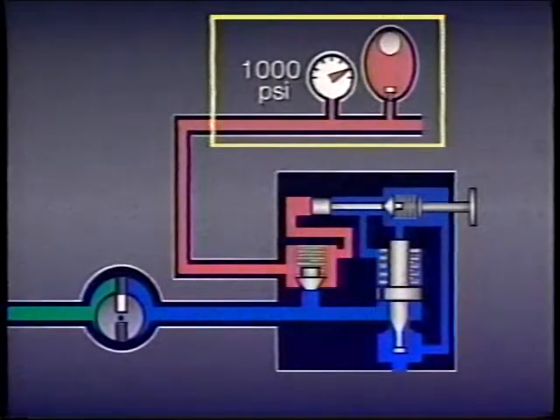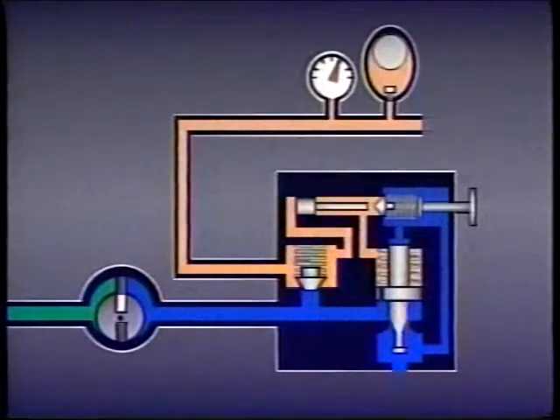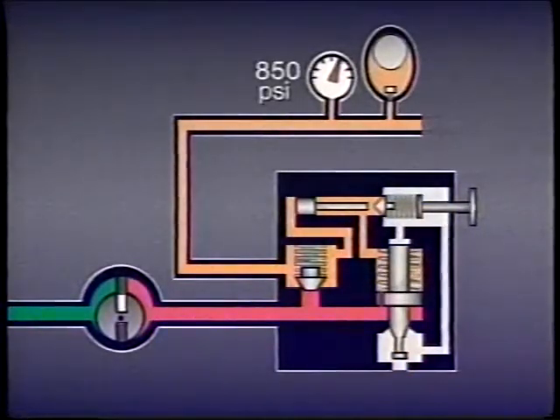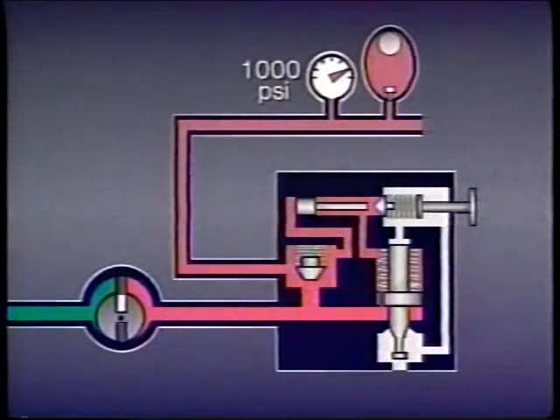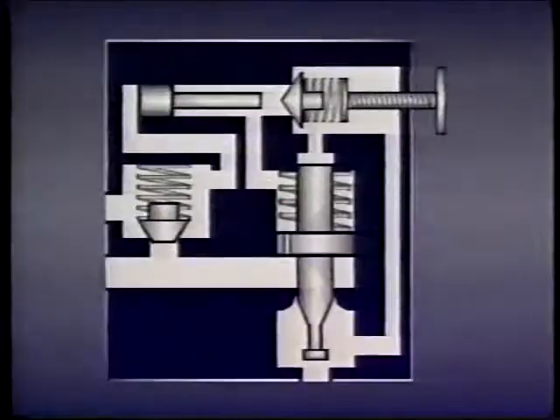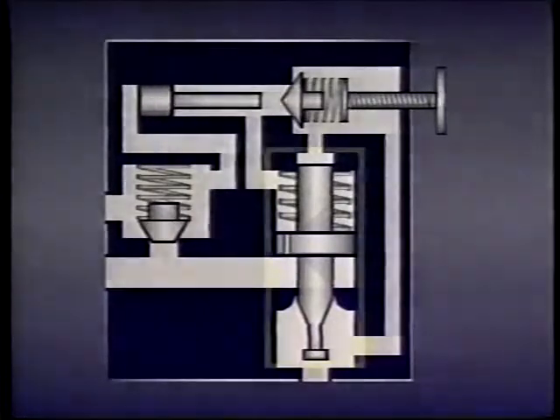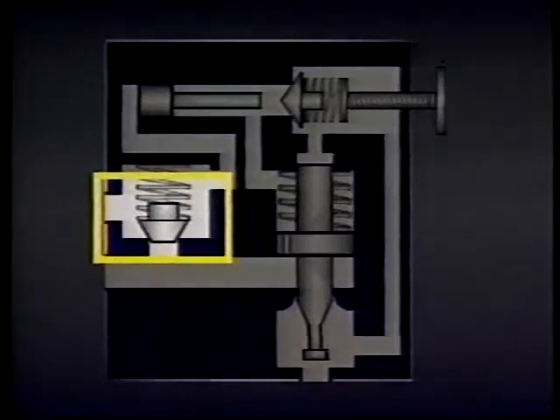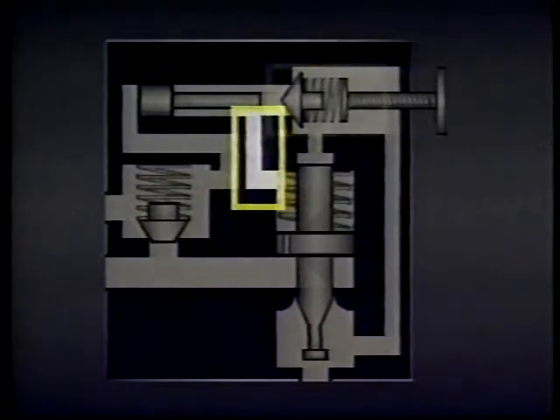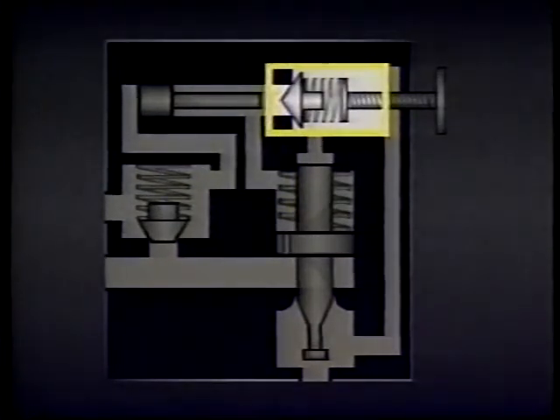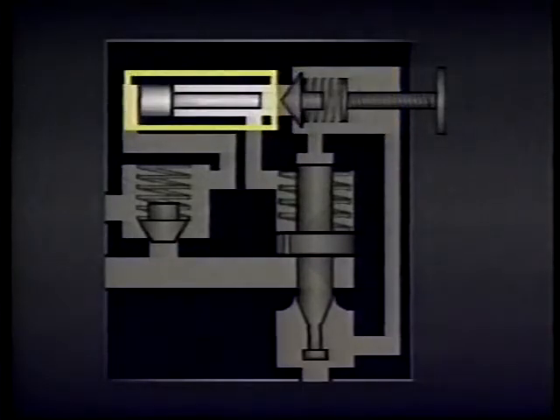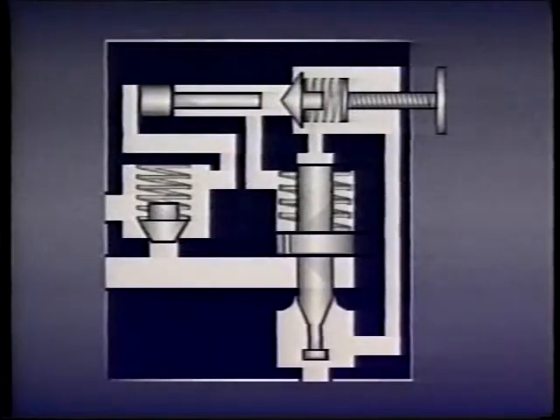In this system, the valve opens and unloads to tank when the accumulator is fully charged at 1000 psi. As the energy in the accumulator is used up, pressure upstream of the check valve drops. When pressure drops to 850 psi, the valve closes and flow from the pump fills the accumulator again. This special relief valve includes a main valve spool, a check valve, a pilot line, a spring-biased pilot valve dart, and a differential piston. They work together to enable the valve to open and close as pressure rises and falls.